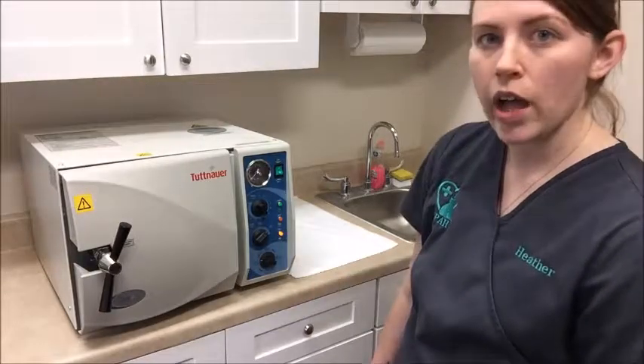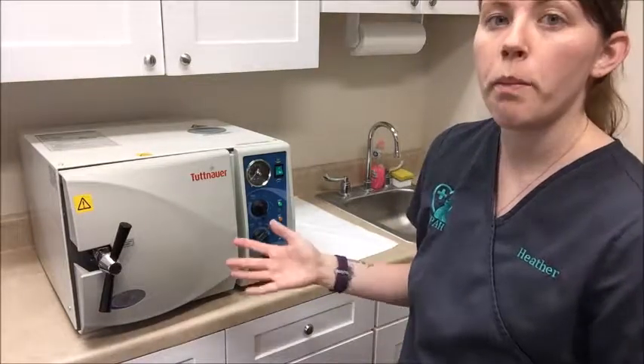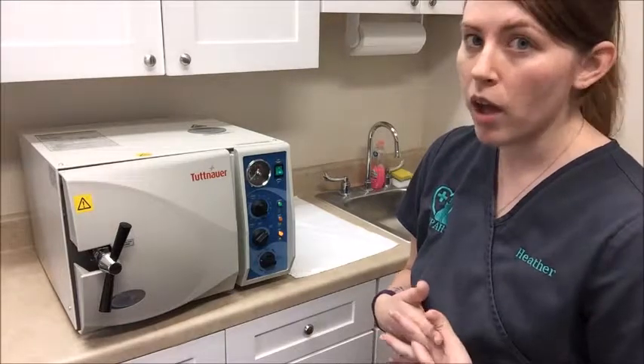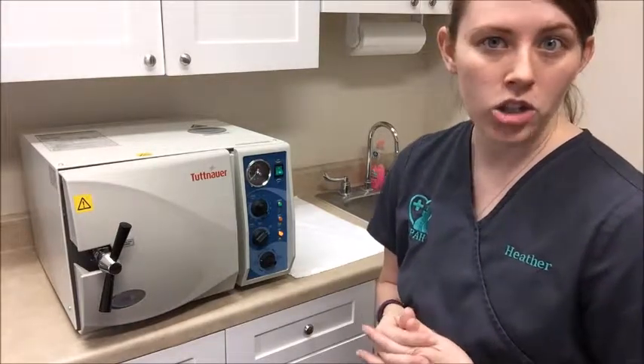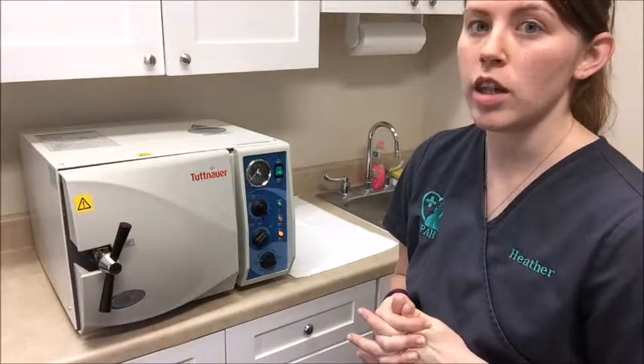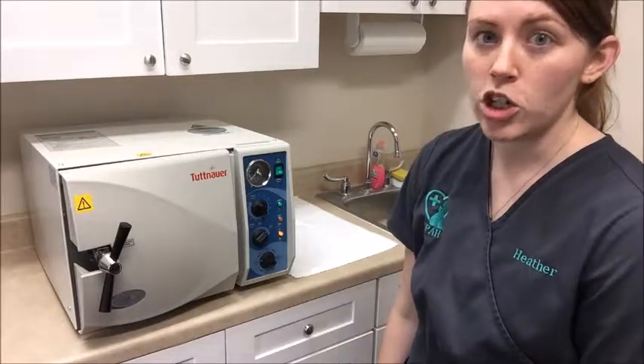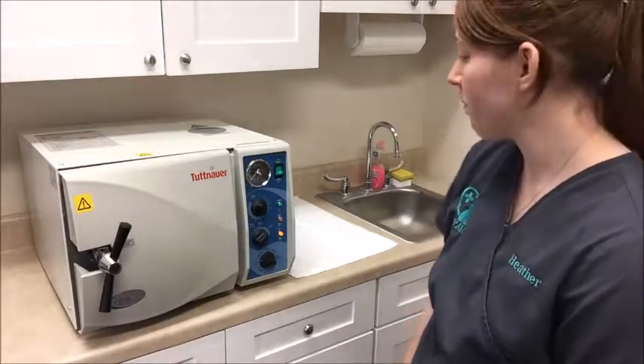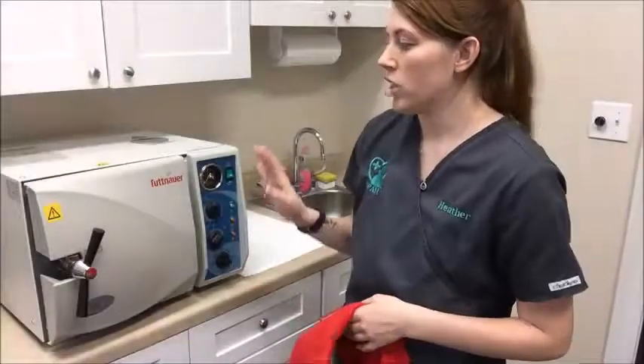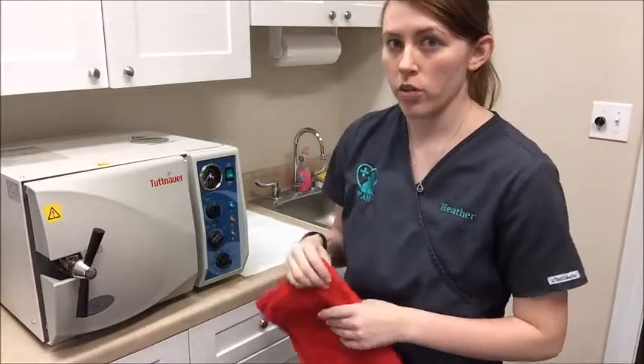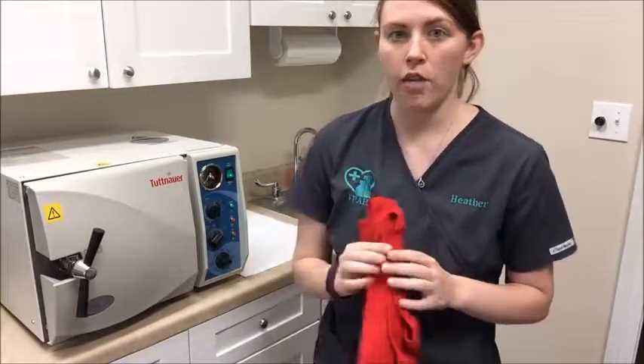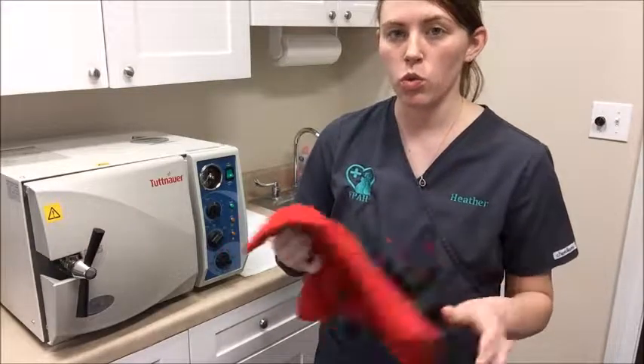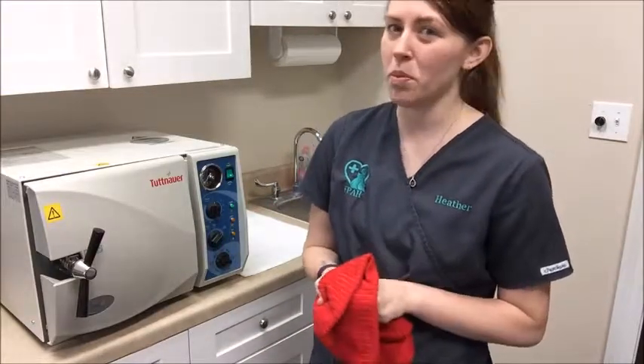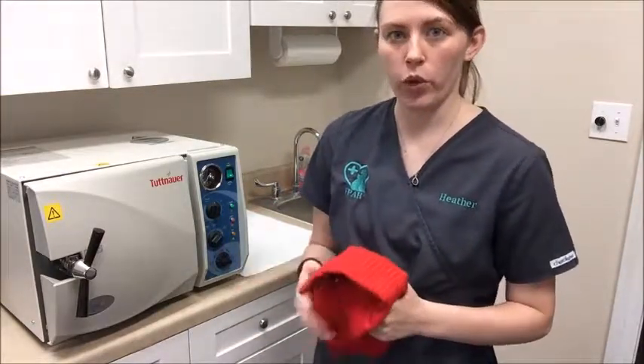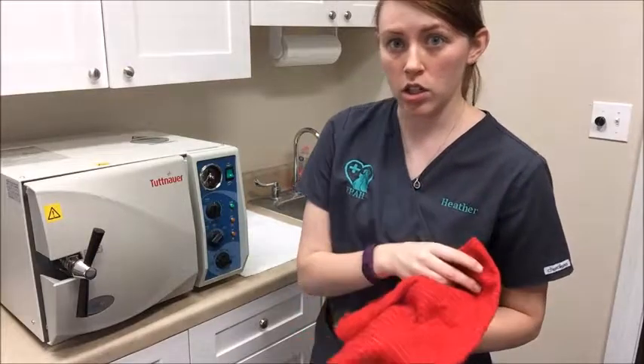So once my drying cycle is complete, I can go ahead and remove the surgery pack from the autoclave, and then I can open it to check the steam indicator to make sure that the inside of the pack has reached the appropriate steam as well. My 30-minute drying cycle just finished on my autoclave, so it is ready for the pack to be removed. I have a nice thick towel ready to take the pack out just because it can still be incredibly hot even after going through that long of a sterilization cycle.